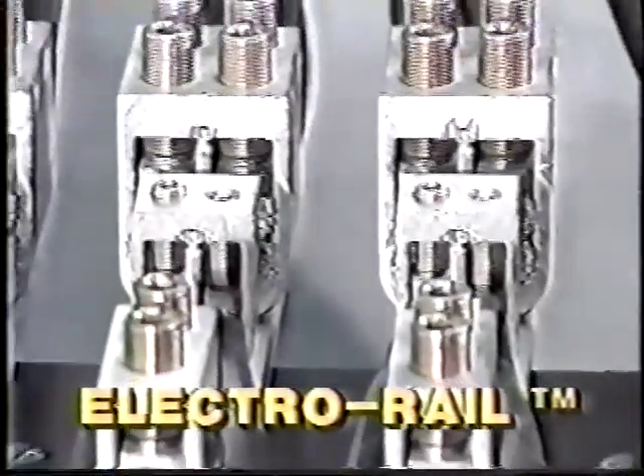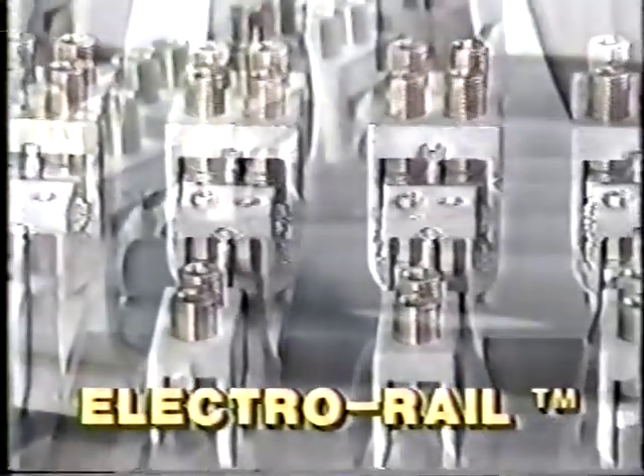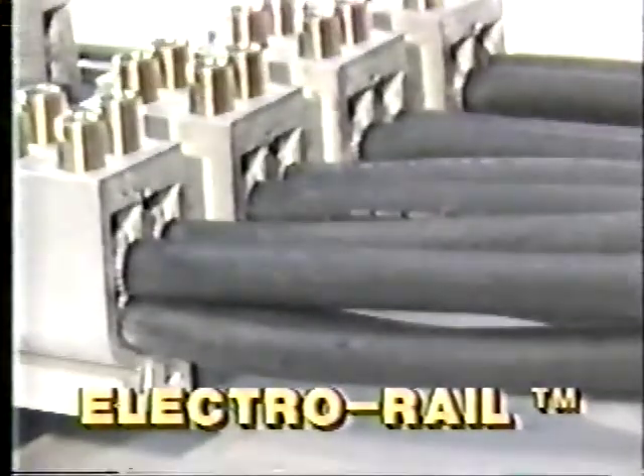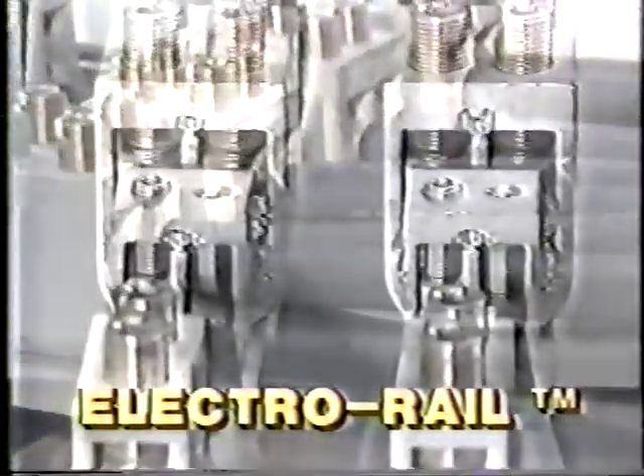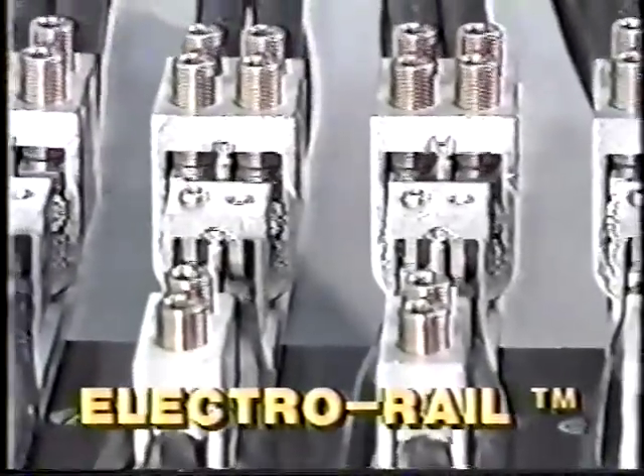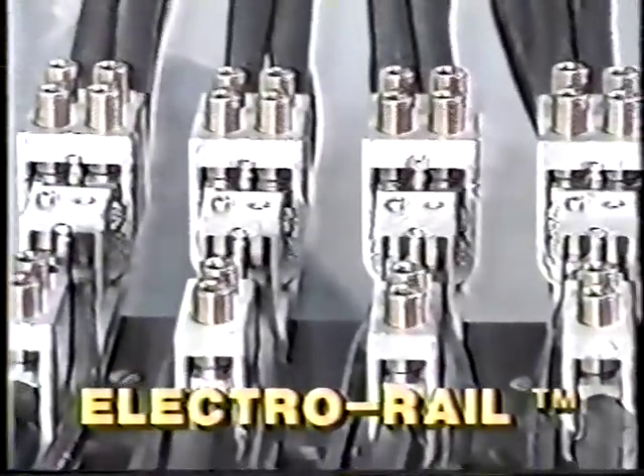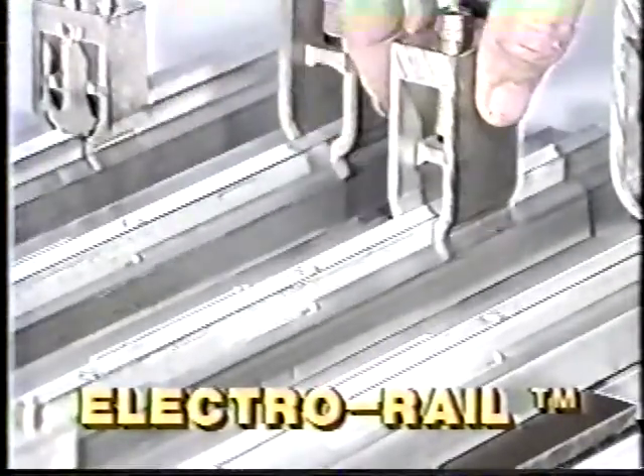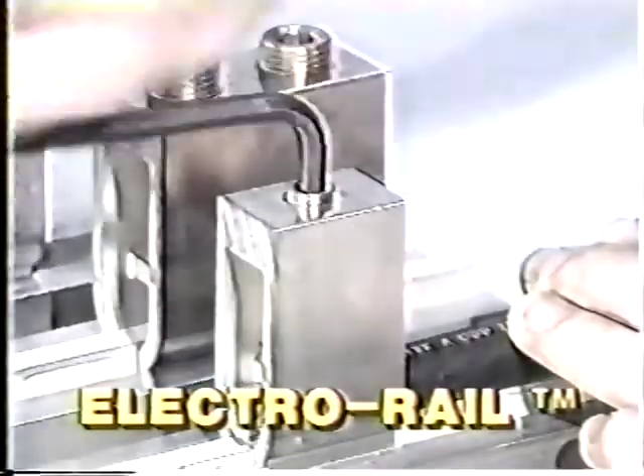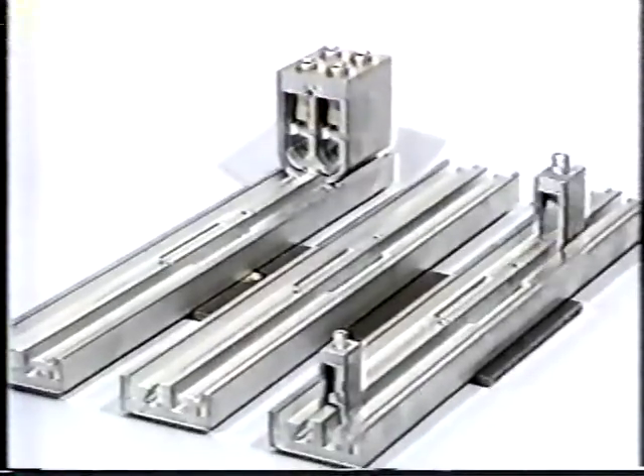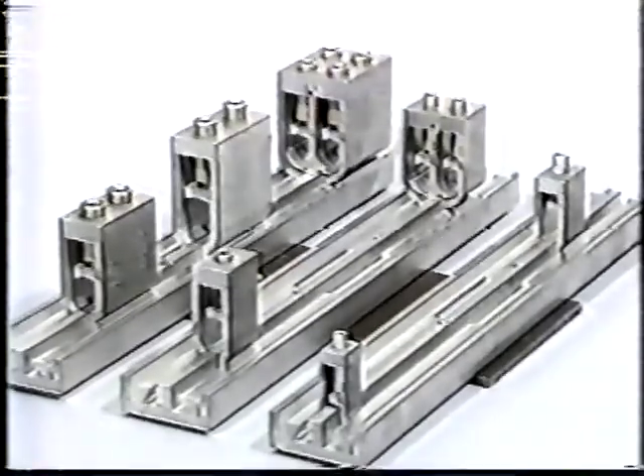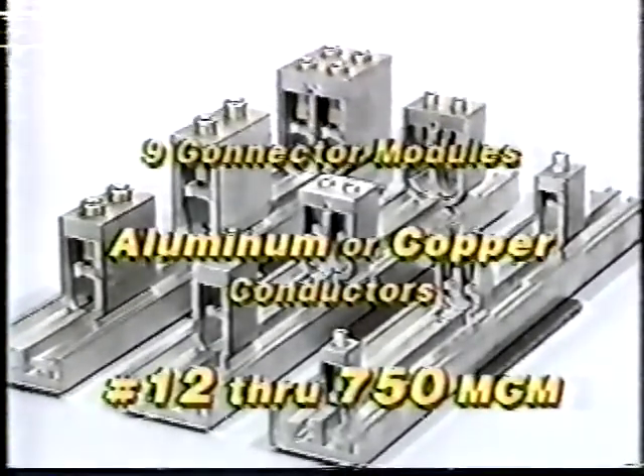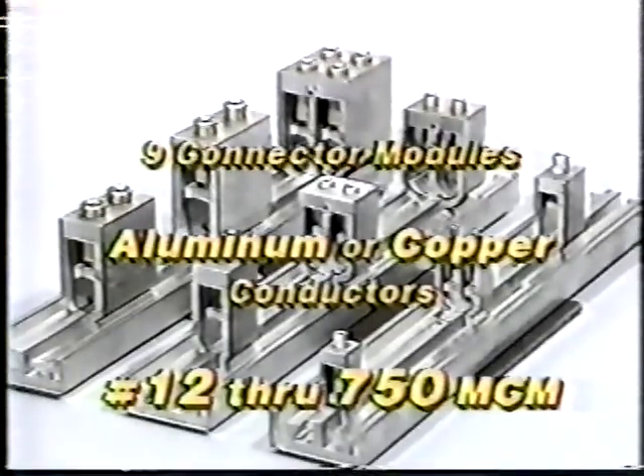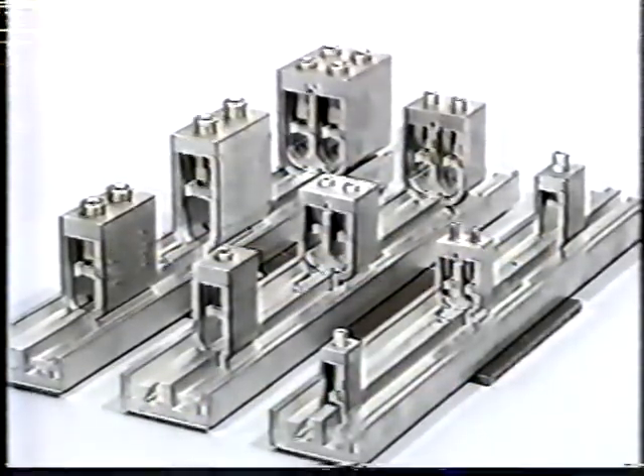Our ElectroRail system provides you with the ability to handle up to 4 feeders per phase. With this system, virtually unlimited tapping is possible in an extremely compact space. With ElectroRail's modular design, modifications and changes are merely a matter of sliding on another connector and tightening the screw. Burndy's ElectroRail connector modules are off-the-shelf components. Just 9 connectors enable you to accommodate aluminum or copper conductors ranging from number 12 all the way up to 750 MCM. As with the whole FlexiTap system, this line is UL listed for up to 600-volt applications.